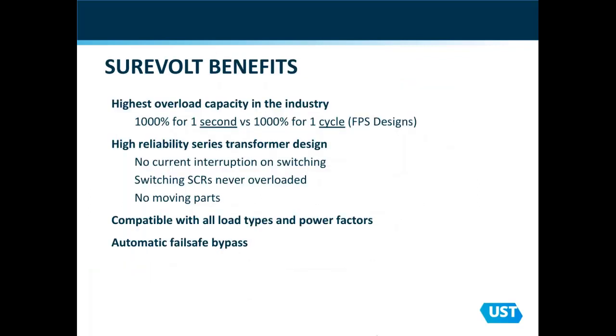So benefits of the Surevolt: we have a very high overload capacity. There's no interruption of switching. SCRs are never overloaded. We have no moving parts. We're compatible with all load types. And again, we have an automatic fail-safe bypass. The bypass is there in case there is some kind of unit failure. We're able to trip to bypass immediately and maintain the load. Other products in this category may, when they have some sort of internal failure, take the load down with them. We don't do that. We have a bypass arrangement that will maintain the load, albeit with unregulated voltage.